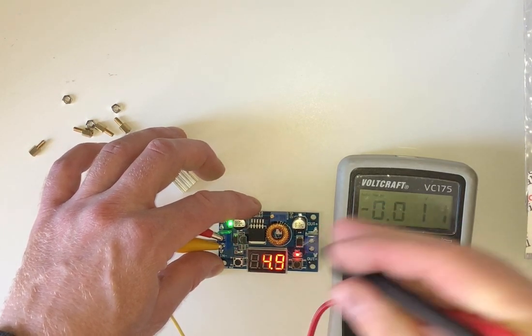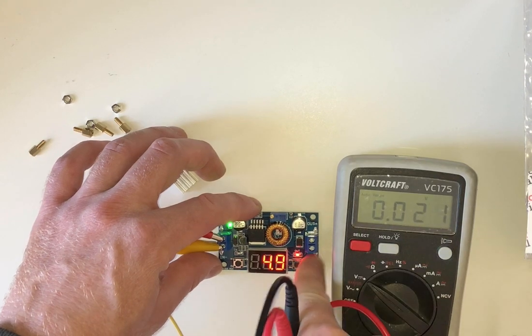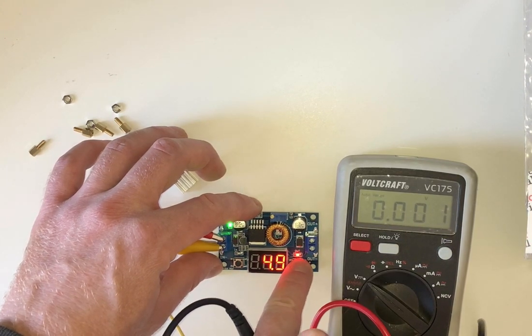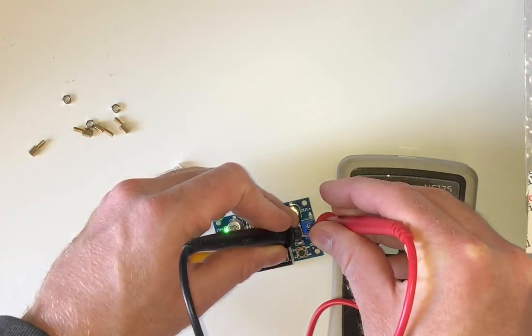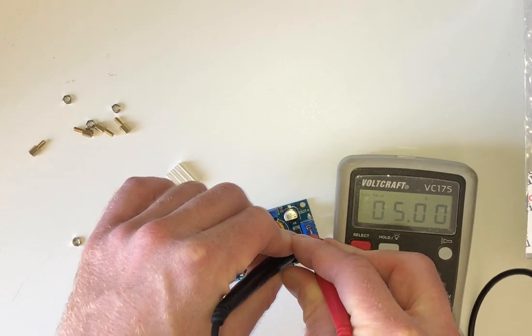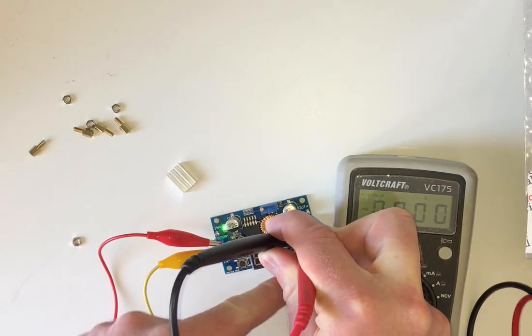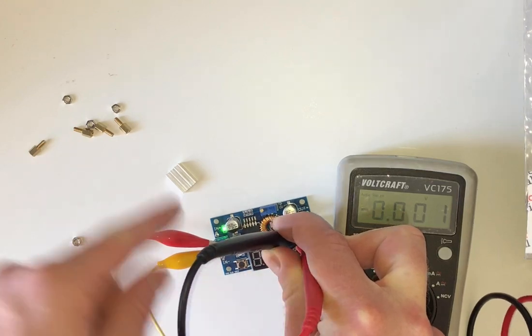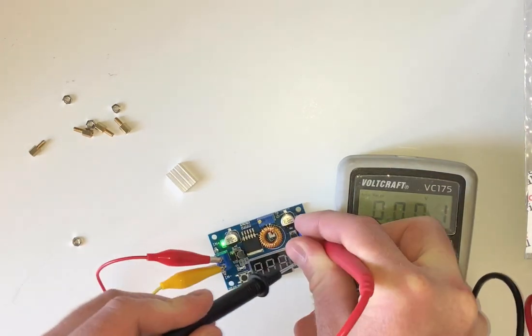And now to measure, and then you do the same, you can calibrate the output voltage. So we hold for three seconds and now we measure this voltage. And now we twiddle these buttons up and down until this display voltage matches what's on my multimeter.